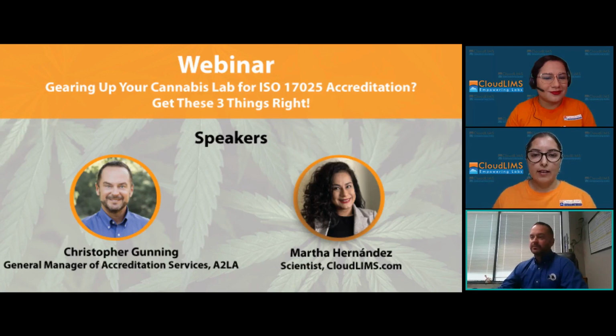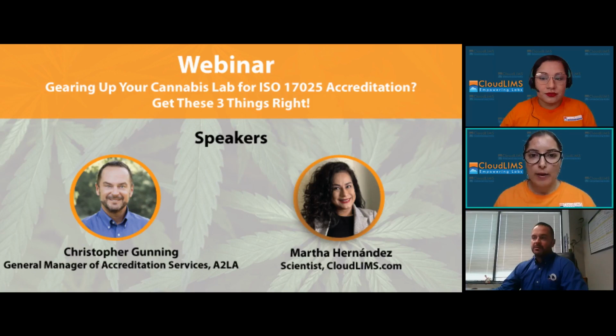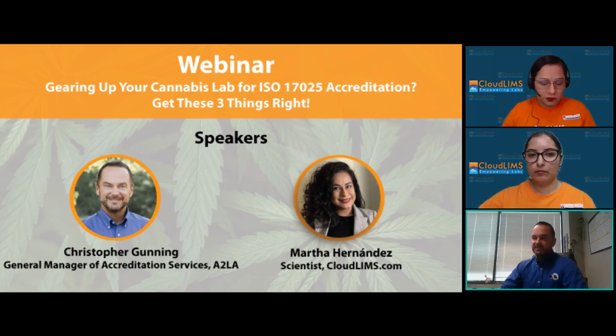Thanks, Chris. Quickly moving on to the next question. Can you explain how measurement uncertainty fits into the accreditation process? Sure. This is covered in Section 7 of the standard when we're talking about methods, method validation, and then measurement uncertainty obviously comes in. So any quantitative method within the laboratory is going to require the lab to calculate their measurement uncertainty. And regardless of whether they report it out to their customer, it must be calculated for all methods so that we can determine how accurate your methods are.